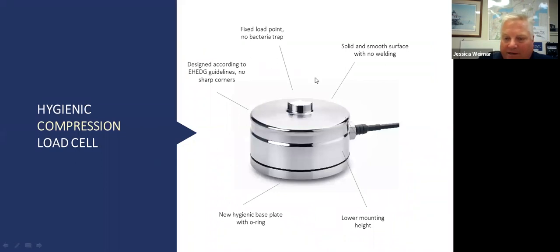If you're considering a compression style load cell, these are some things that people like about them. They're designed according to EHEDG guidelines. These radiuses are made to meet their requirements. There are no bacterial traps in here, and that's important. You may see a strain gauge load cell that has a similar look to it, where you see this button in the middle. But a lot of them, this button is a separate piece and sits down inside of a well inside the cell. And that well can be a bacterial trap. We don't have that. This is an absolutely smooth surface. The entire surface deflects under load.